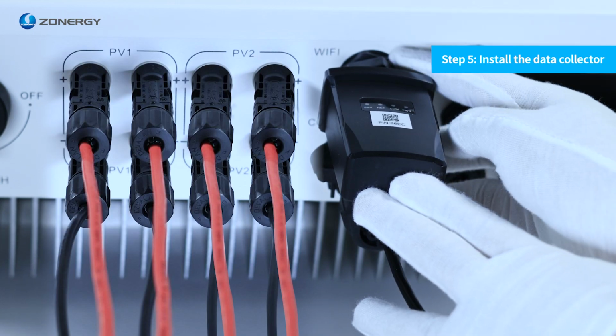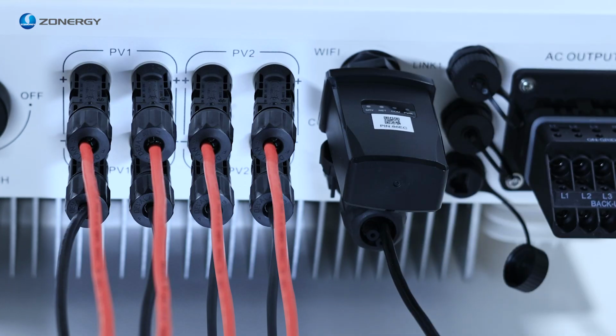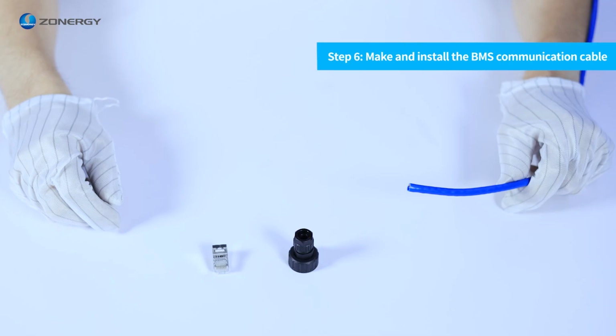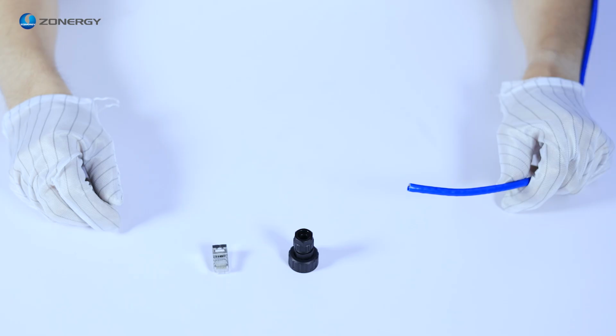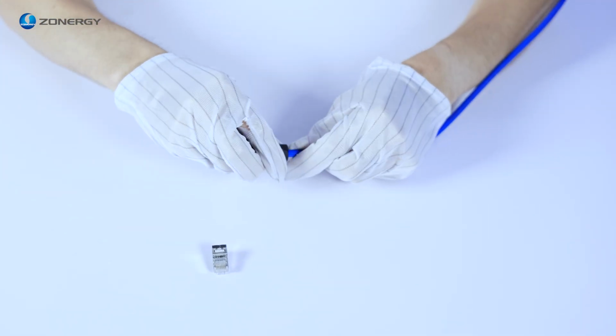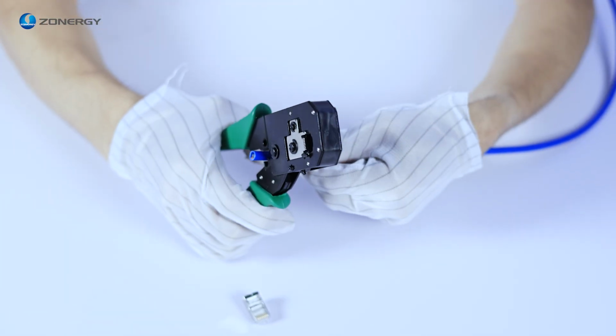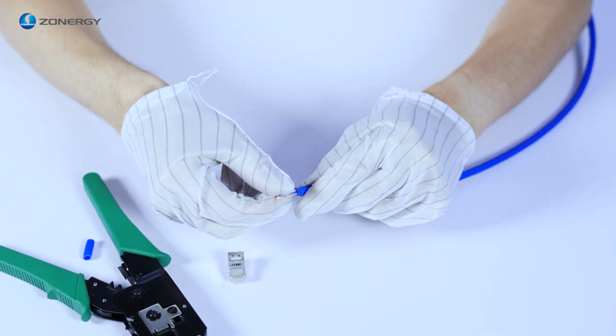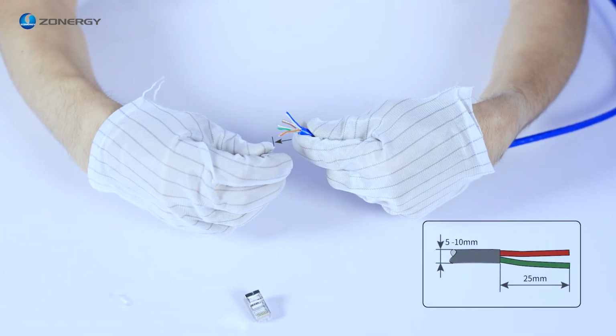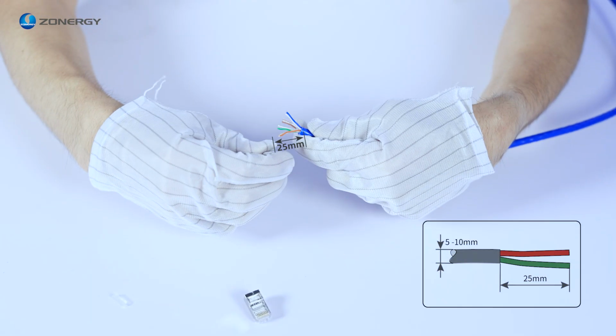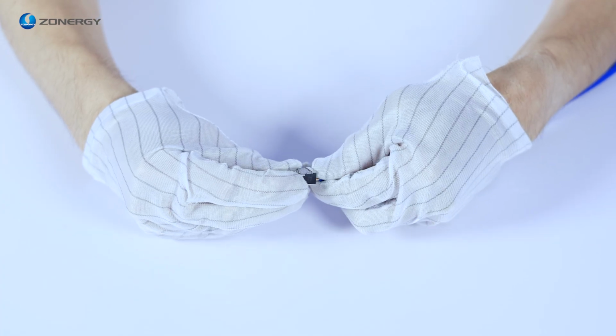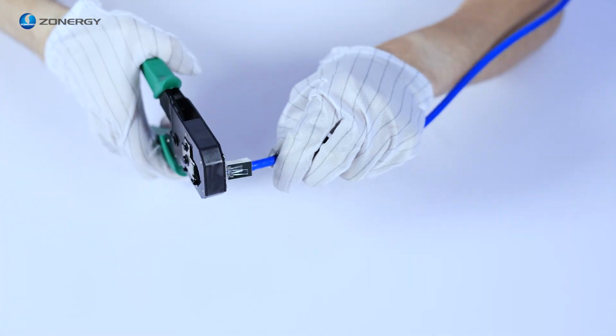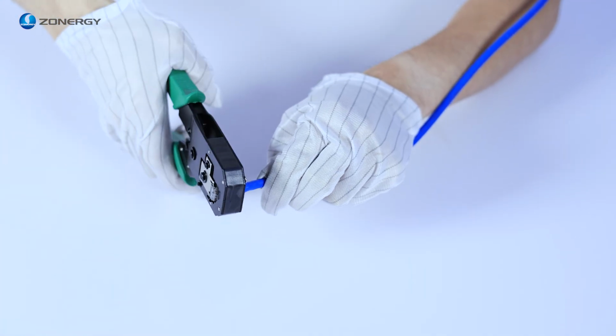Step 5. Install the data collector. Step 6. Make and install the BMS communication cable. 1. First pass the cable through the BMS connector. Please make a cable connector of appropriate length according to the mark. Insert the cable into the RJ45 connector. Press the cable with crimping pliers. Tighten the screw.